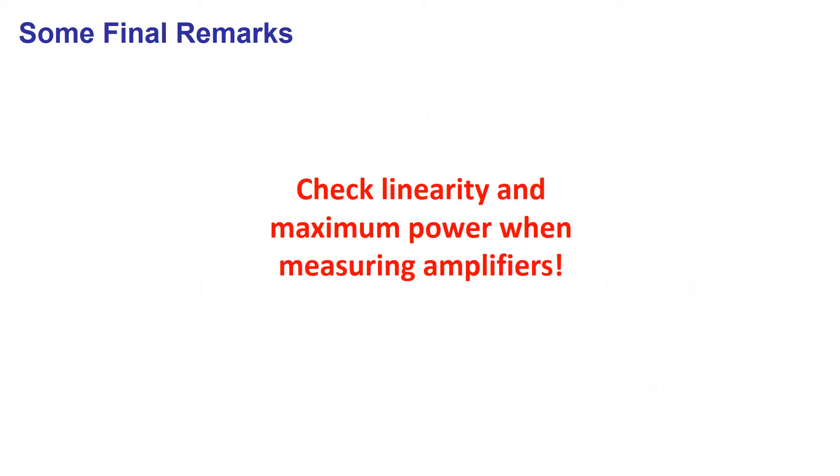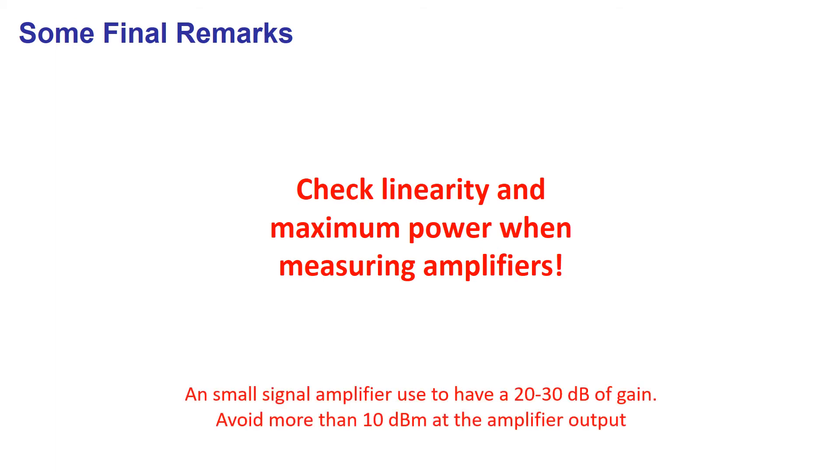You should check linearity and maximum power at the instrument ports when measuring amplifiers or other devices with gain. You might need to reduce the power of signals generated by the analyzer.